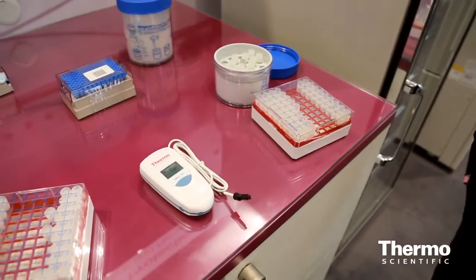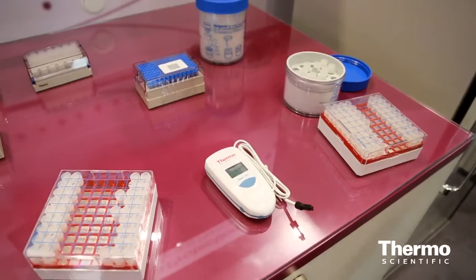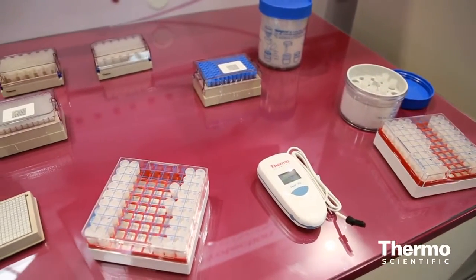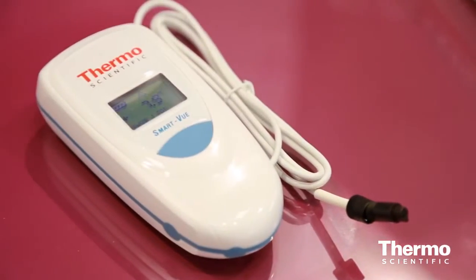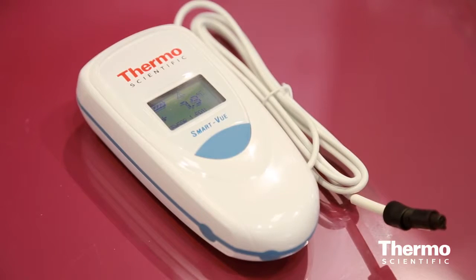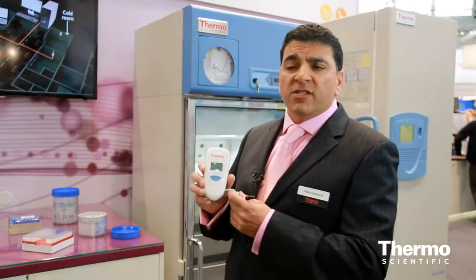Basically you have a transmitter and a probe which goes into the chamber. It's not attached to the instrument in any way whatsoever. It has an internal battery which lasts for 5 years, and it's collecting data every 5 minutes or whatever timeline the scientists wish to take. It gets collected onto a server and then it goes on a graph, and you can access this remotely via the World Wide Web. Thermo Scientific Smart-Vue will actually link most of your instruments within the lab.